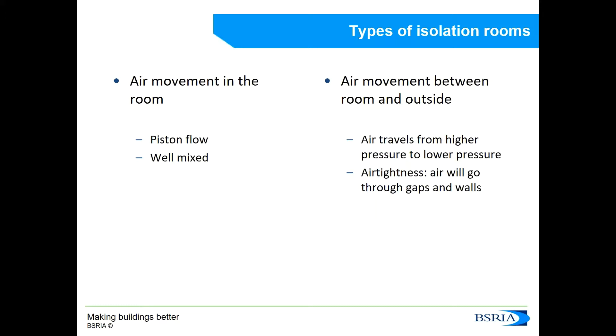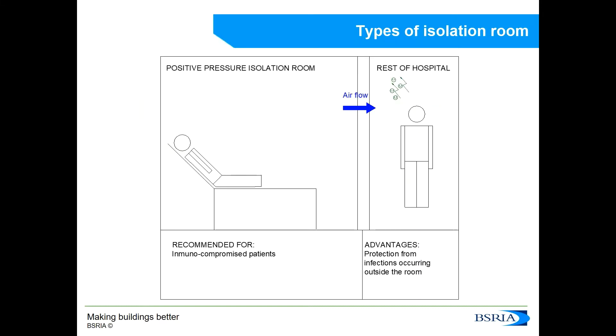When it comes to the relationship between the air in the isolation room and the rest of the hospital, air travels from higher pressure areas to lower pressure areas and will find any small hole to escape, even through the fabric of the walls. This is why air tightness is so important. What you can see here is how we use pressure differentials in a positively pressurized isolation room to protect an immunocompromised patient, making sure that air travels from the room into the rest of the hospital and not the other way around.